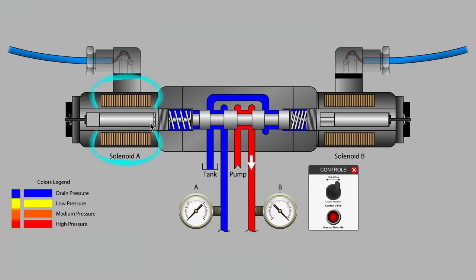The armature slides easily in a tube that is internally lubricated with hydraulic oil. The armature moves the pushpin, and ultimately the pushpin moves the valve spool. And now we see flow from the pump being directed to workport B.